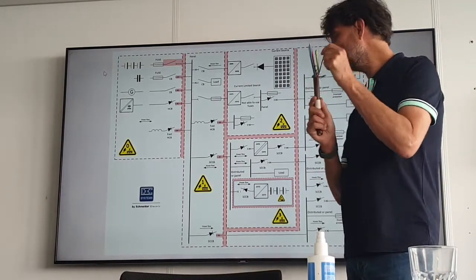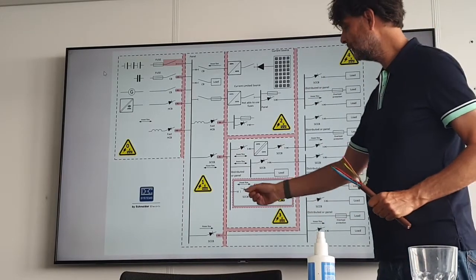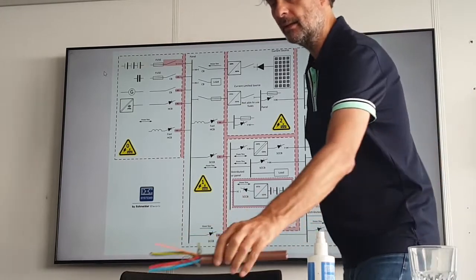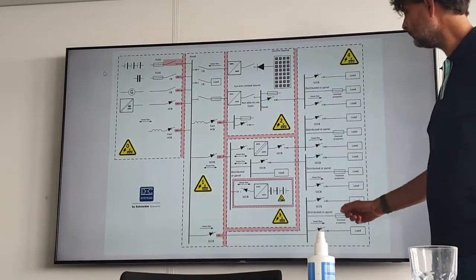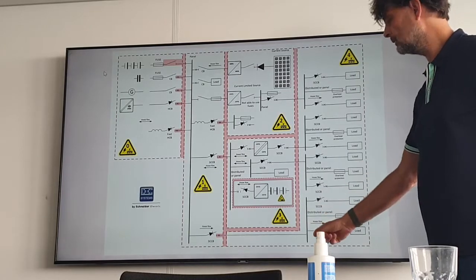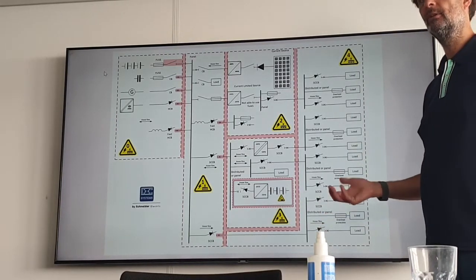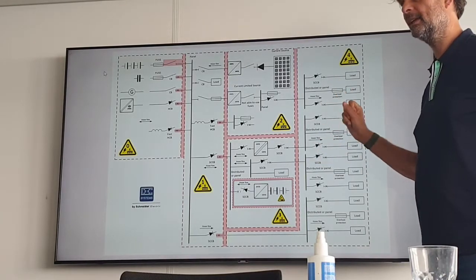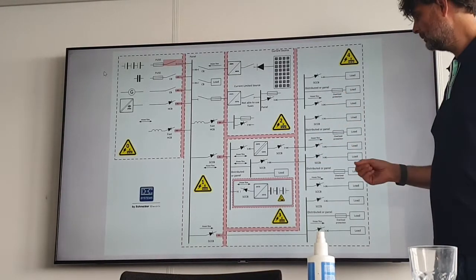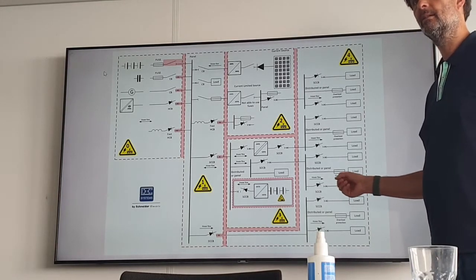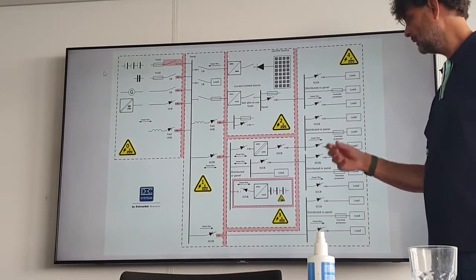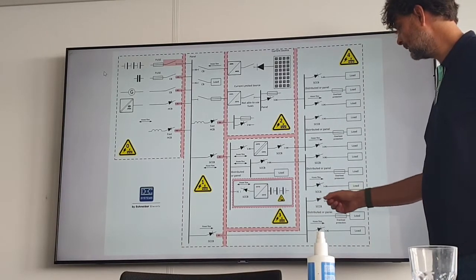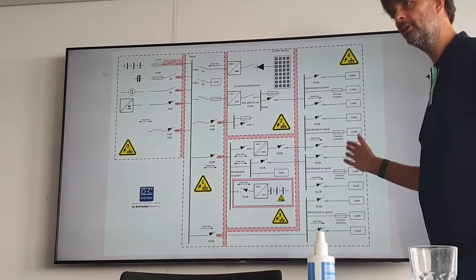So this is the safety wire, and in the safety wire, you disconnect all the sources. That's why this is a zone 3 cable. And in zone 4, we have simple final circuits with only loads, so there's only one source. But here we have all the protections you can think about. That means to make risk low here, because it's simple, one source, it's fully electronically protected. It has RCD functionalities, it has whatever you can think about.